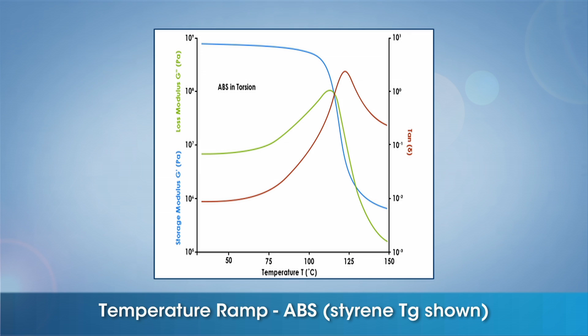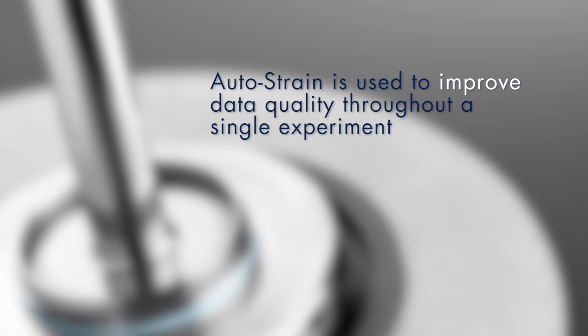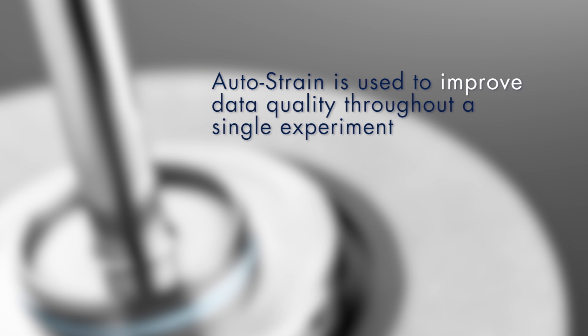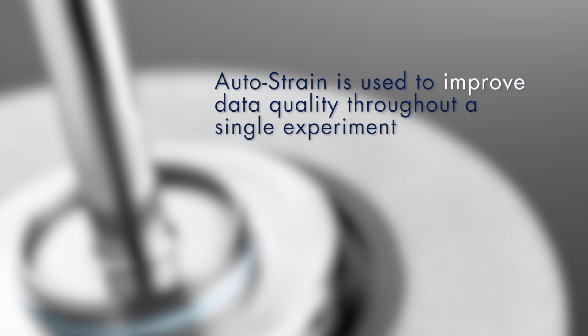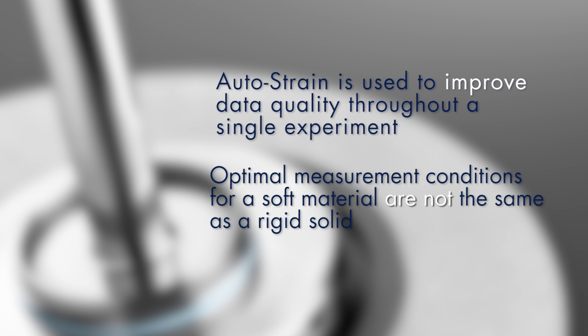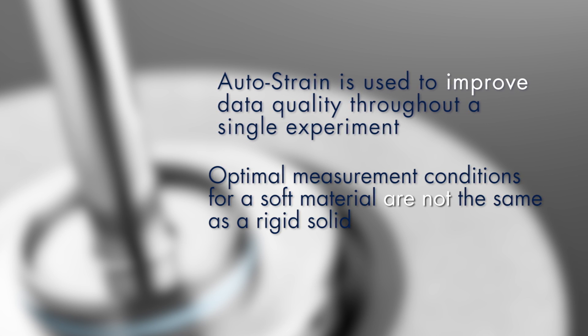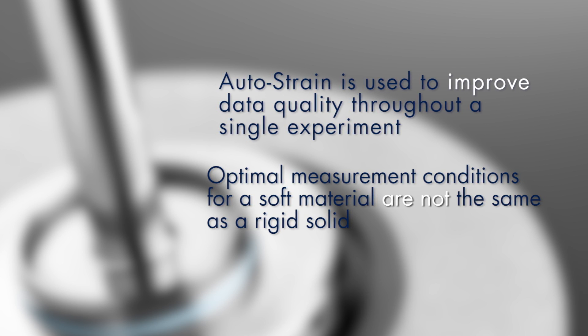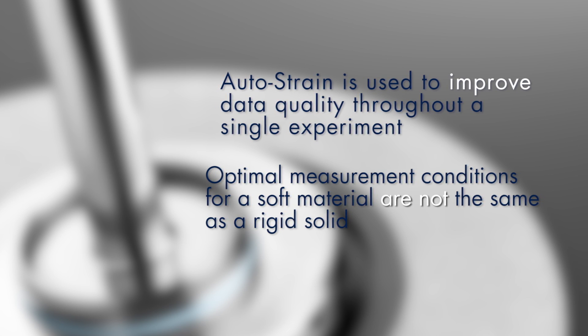The Auto Strain function works by automatically adjusting the strain amplitude during an oscillation experiment in order to maintain the measured torque within a given torque window. In more simple terms, Auto Strain is used to improve data quality throughout a single experiment, since optimal measurement conditions for a soft material are not the same as for a rigid solid.